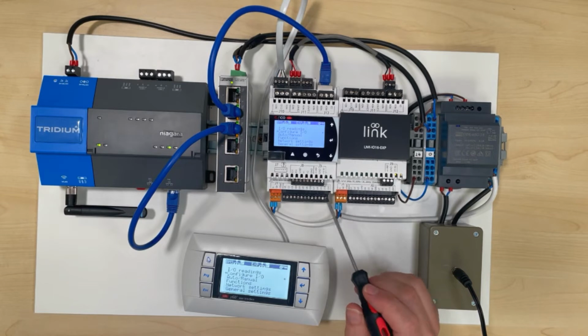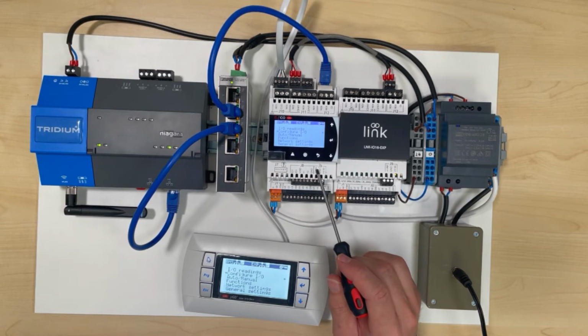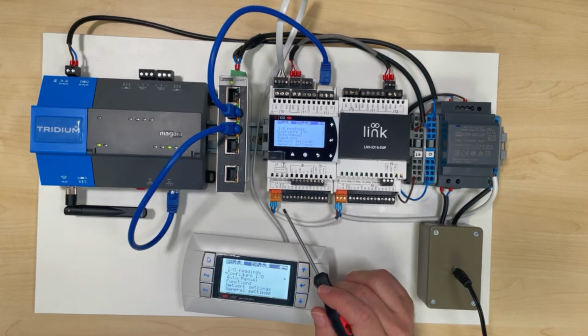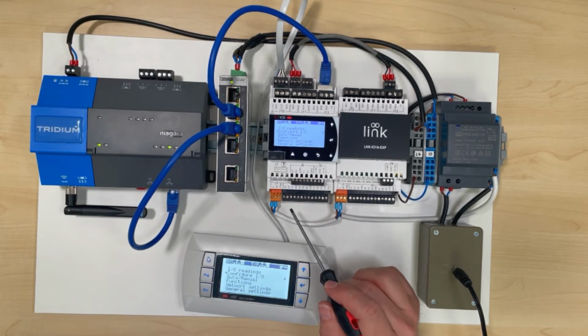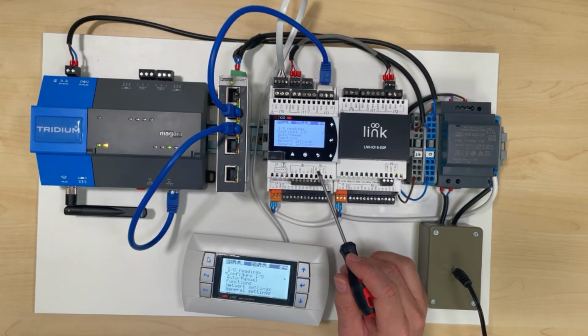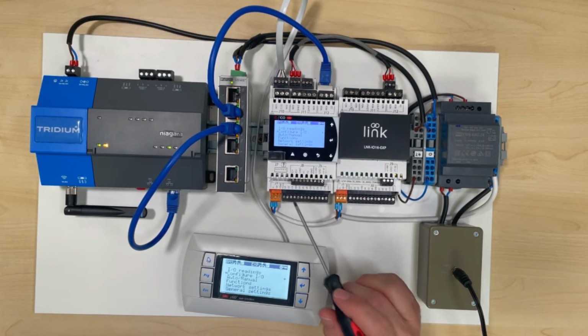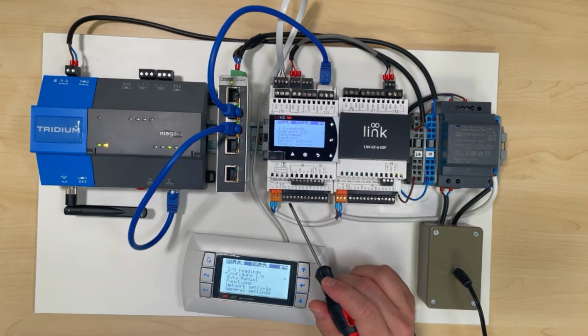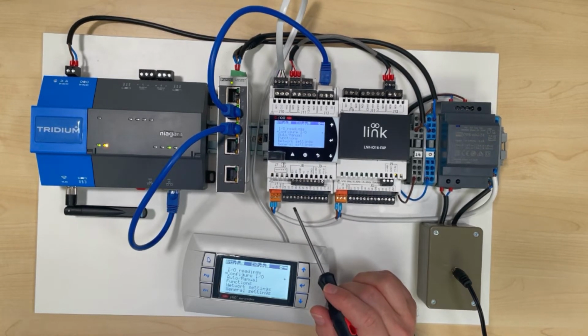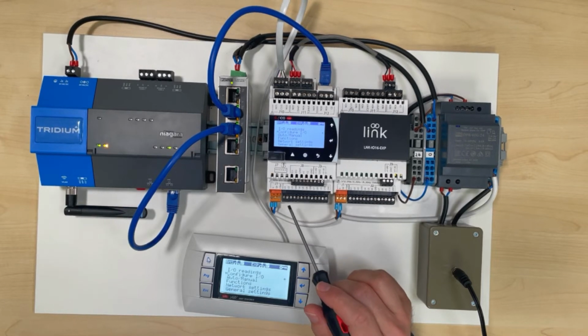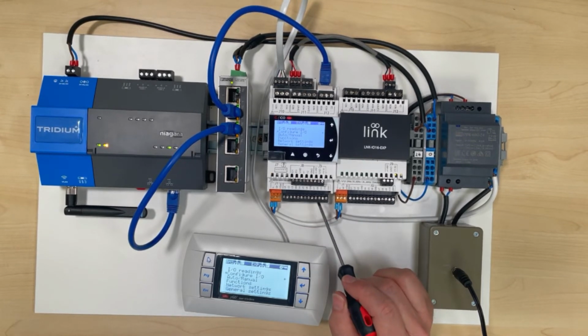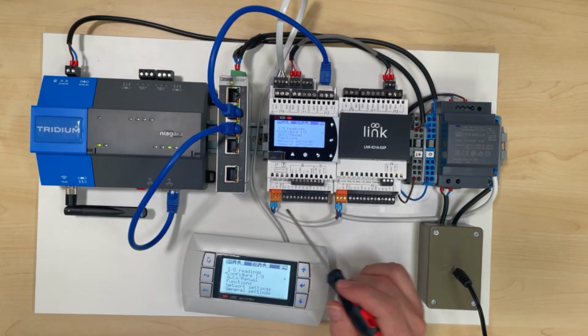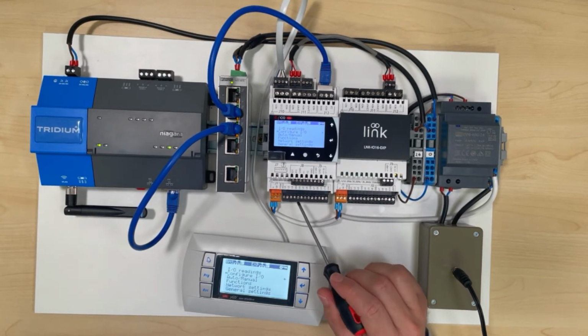If you use 0 to 5, there is a 5 volt reference here you'll see on the IO20. That can be used to go through something like a potentiometer to vary a 0 to 5 volt signal. If you use that 5 volt reference, you have a limit of 2 maximum 0 to 5 volt inputs, so you need to take that into account. 0 or 4 to 20 milliamp, there's another limit on there. You can have a maximum of 4, so you need to take that into account when you're pricing up jobs and project engineering your panels and things like that.